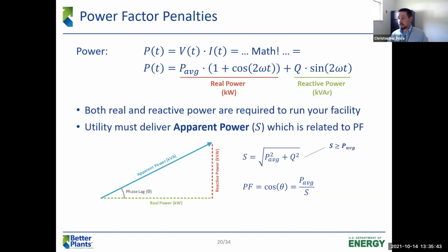What you'll notice is that the apparent power is the same as the real power or more. The more phase lag you have, the lower your power factor, and essentially the more apparent power the utility has to supply your plant. So for a given amount of real work, the lower your power factor is, the more apparent power the utility has to supply.